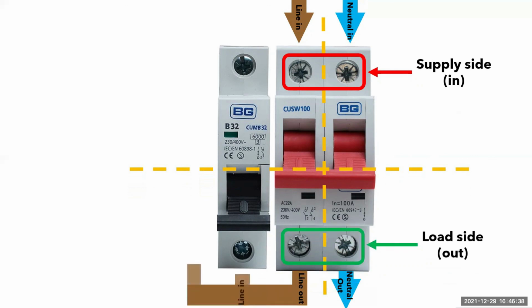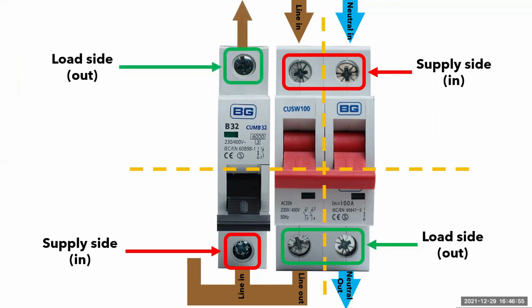If we now bring the bus bar in, you will see that the pin coming out of the main switch is the supply to the bus bar, and the pin going into the bottom of the MCB is the line in. This means that the bottom of the MCB is the supply in and the top is the load out. This should make it easier for you to understand how the switches inside a consumer unit work, and then think about where you are going to put your test probes.